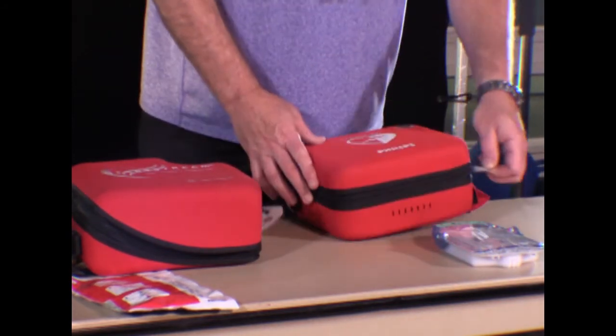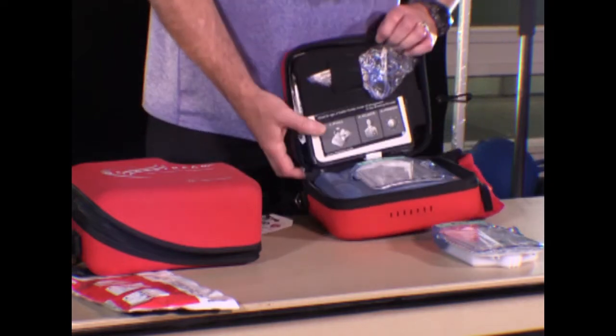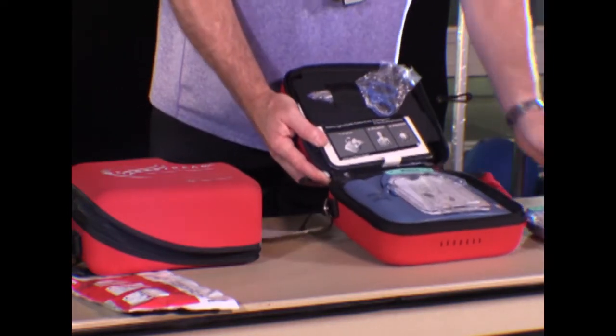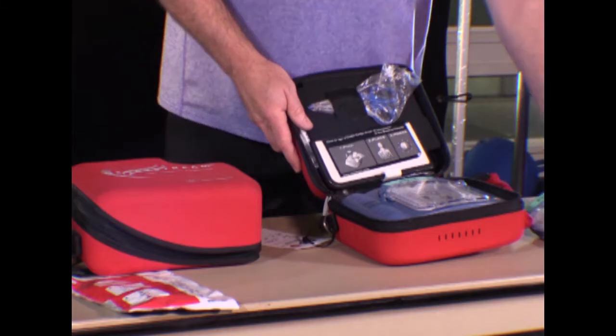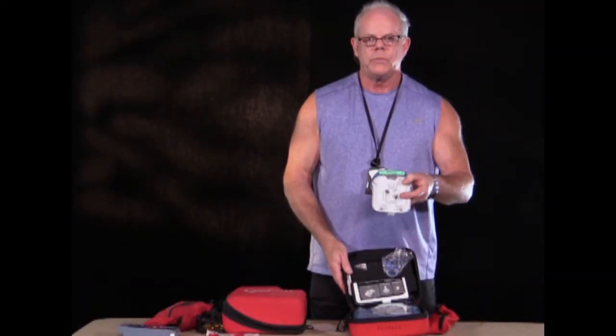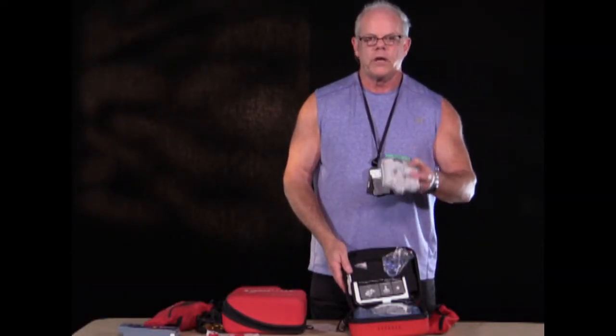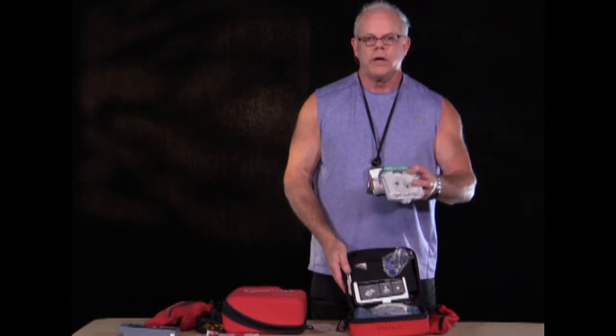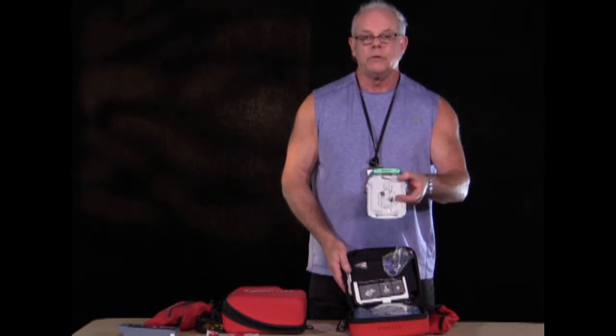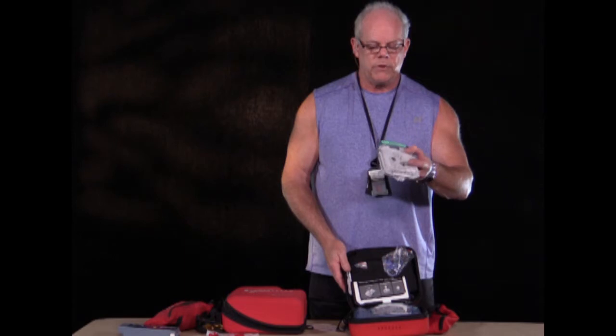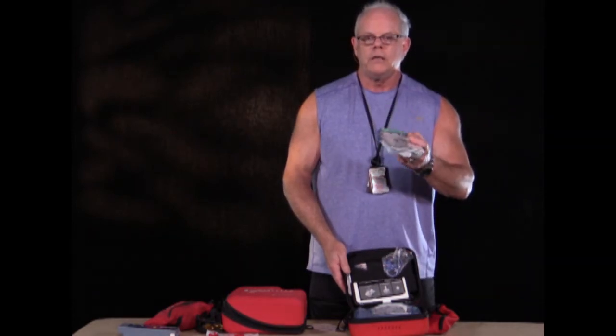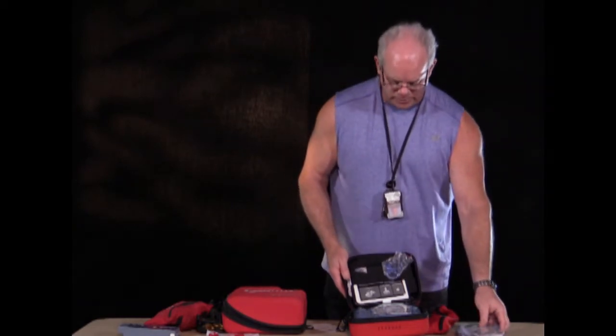So with the on-site defibrillator, we open that up, and what you'll notice right away differently, it opens to the top, and then it has a cartridge in there, which is a little bit easier to use because the pads are in the cartridge, they're connected to the machine, and so they're ready to go just by pulling the little handle that says pull. And here becomes the issue, but even though this is in a sealed container, the gel that's on these pads can dry out over time, and so they need to be replaced properly.